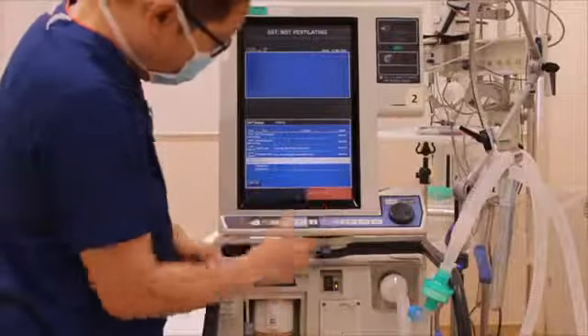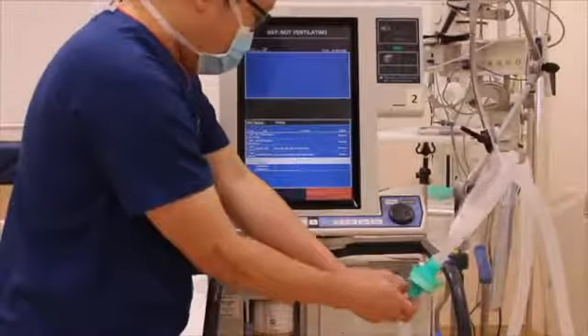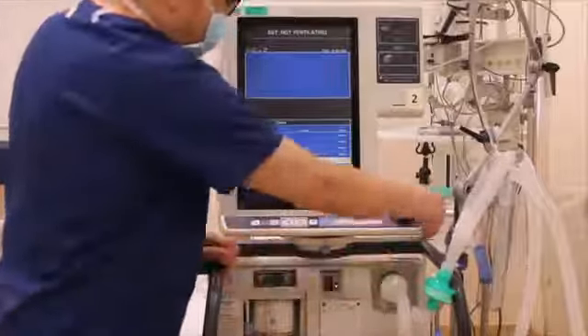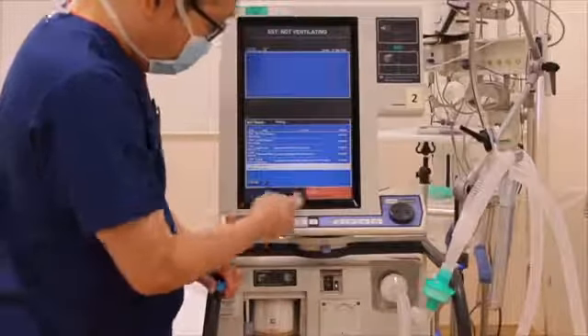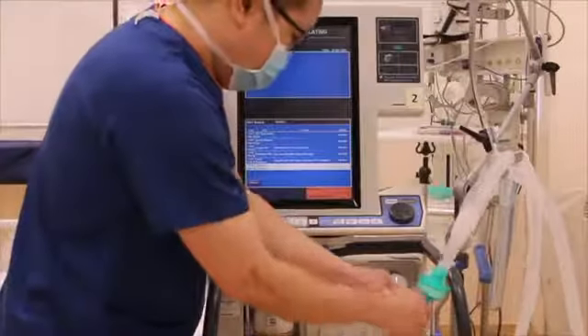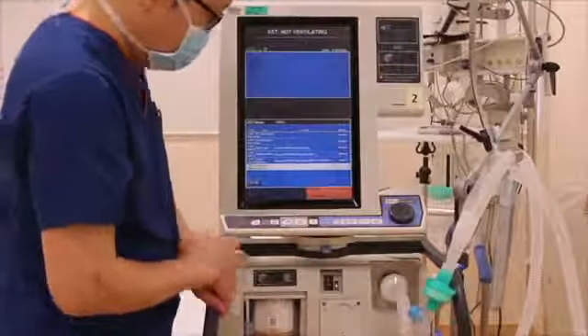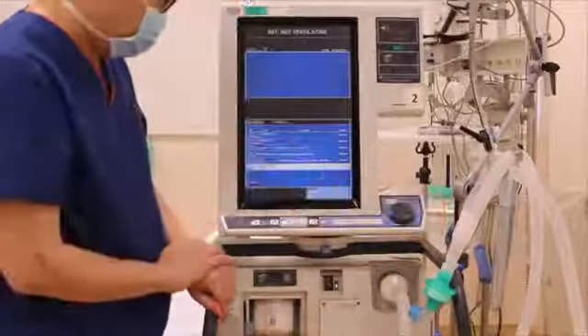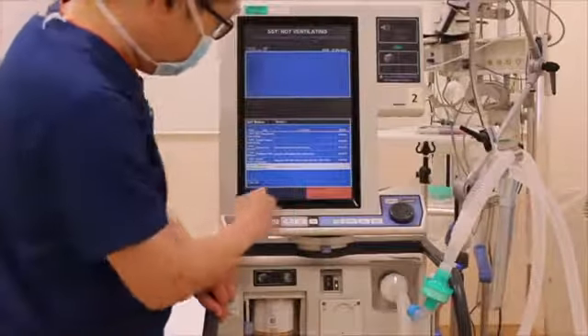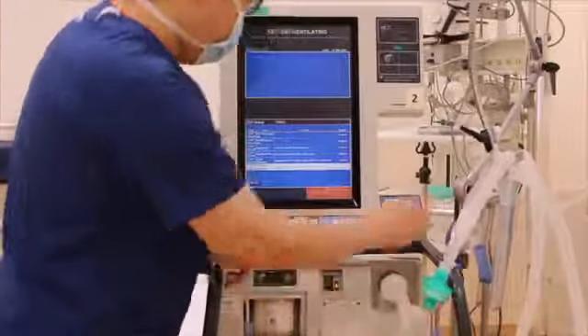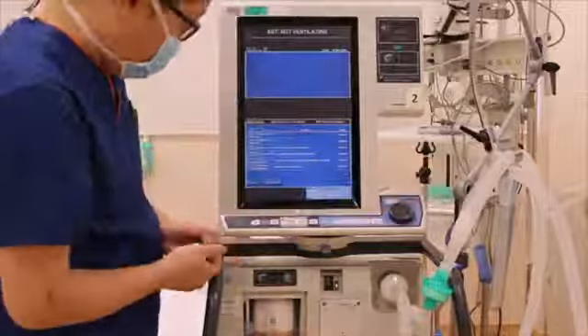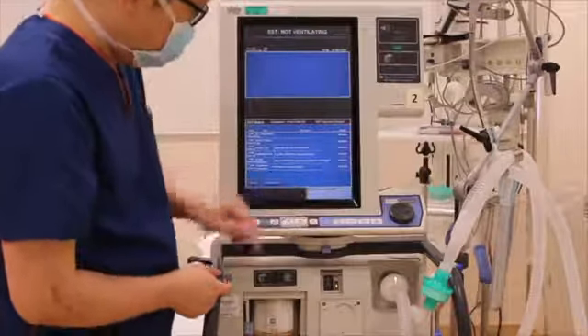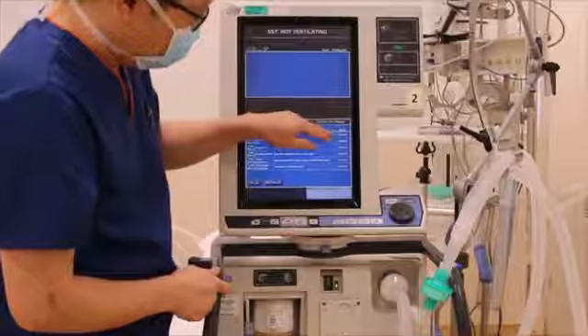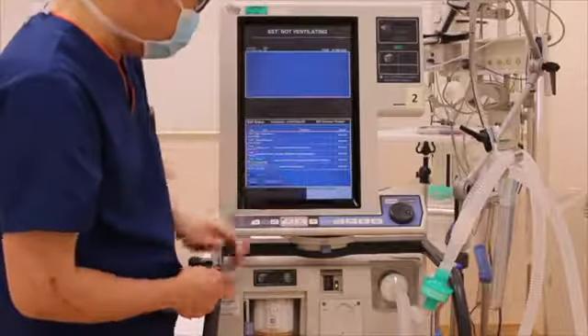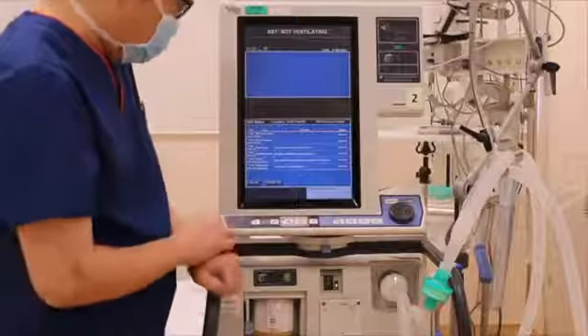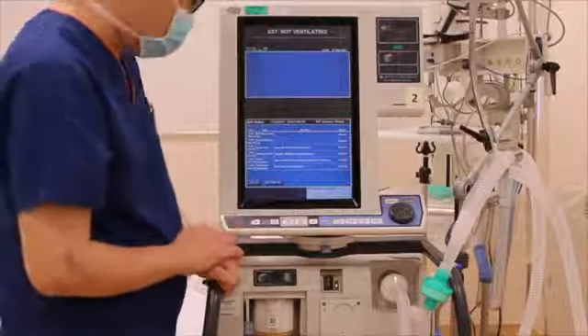So it's now instructing us to unblock the Y connector. So remove the blue cap, press accept. We're coming to the end. So now it's asking us to recap the Y connector. Once that is done, press accept. Okay, it's now asking us to remove the block Y. And you will see that it says the SST testing is complete. And you will also notice that for every step, there will be a tick mark. When that is done, you are ready to proceed to connect the ventilator to the patient.